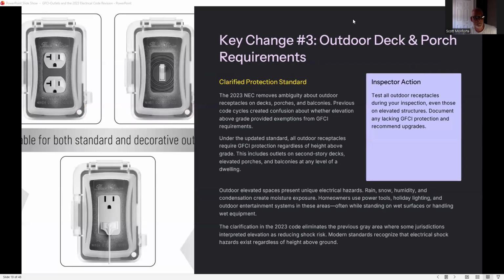Stand out. Key change number 3. Thank you for that, Stan. Outdoor deck and porch requirements. Clarified protection standards. The 2023 NEC removes ambiguity about outdoor receptacles on decks, porches, and balconies. Previous code cycles created confusion about whether elevation above grade provided exemptions from GFCI requirements. Under the updated standard, all receptacles require GFCI protection regardless of the height above grade. This includes outlets on second-story decks, elevated porches, and balconies at any level of a dwelling.